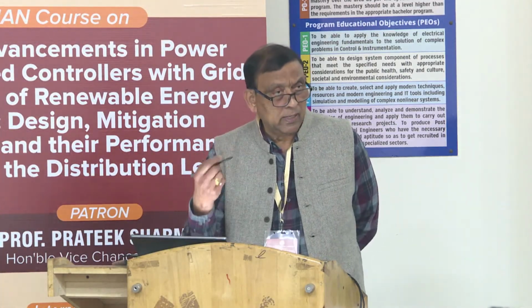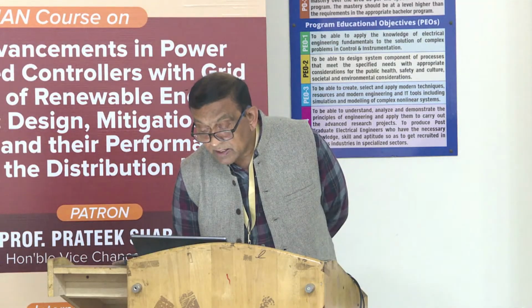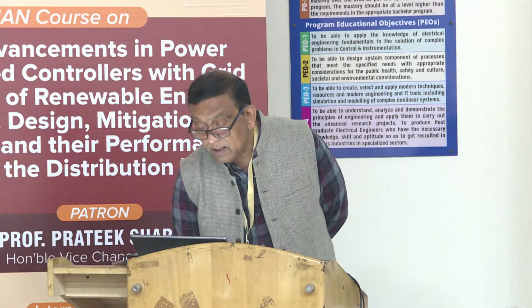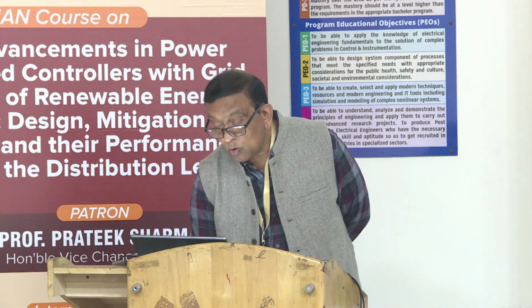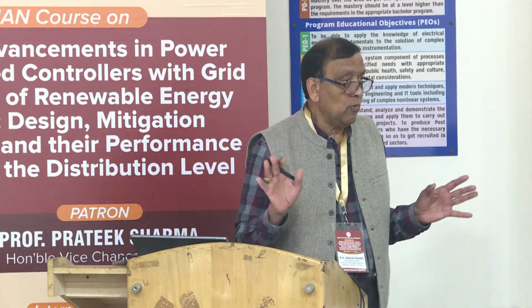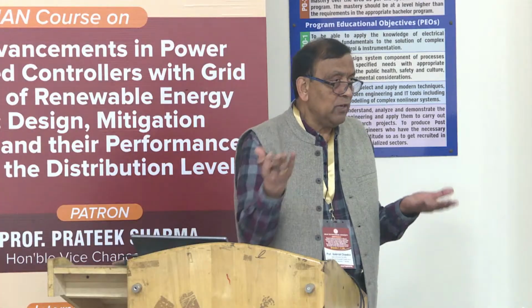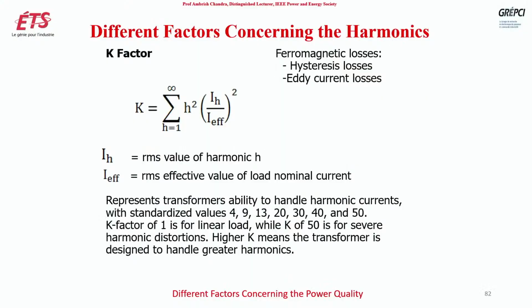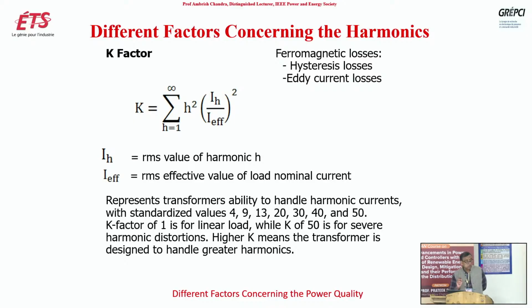And they have standardized values. Engineers in the industry, because you cannot have an infinite number of different transformers, have put K factor values as 4, 9, 13, 20, 30, 40, up to 50. K factor of 1 is for linear load. So you have a simple transformer, balanced system, linear load, so you don't have to worry about harmonics. So you can have K equal to 1, which we generally do even in transmission. While K factor of 50 is for severe harmonic distortions.